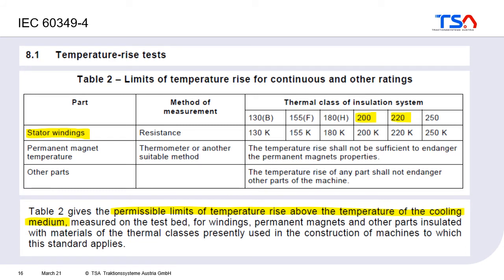The temperature rise test is one of the most important tests for a new machine design. The machine is run for a certain time — sometimes a specified duration like one hour — but most often it is a continuous heat run until thermal steady-state operation is reached. At the end of the test, temperatures throughout the machine are checked, with the stator windings and their insulation being among the most critical parts.